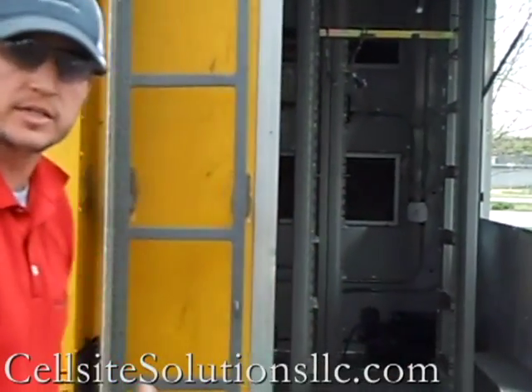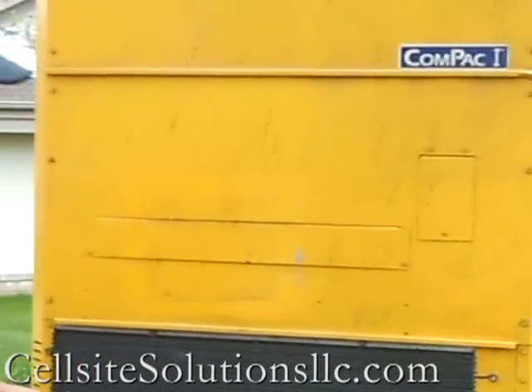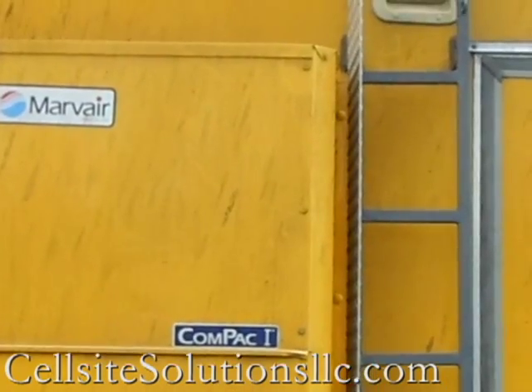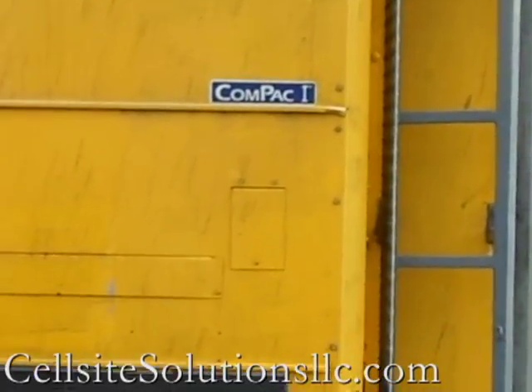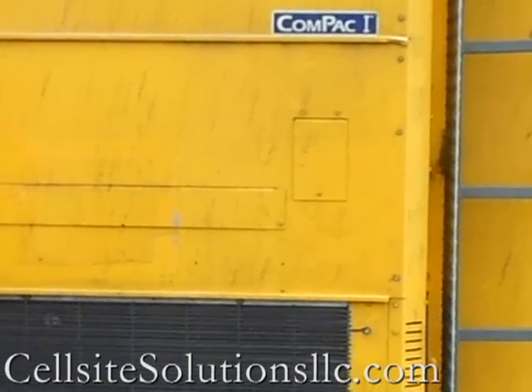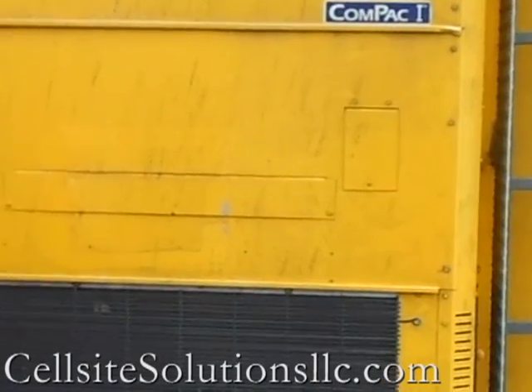There's an easy entry access door here in the back that gives you access to the inside. We've also got a second 3-ton Marvair air conditioning unit back here — these are AVP-36 air conditioning units. They're redundant, with a lead-line controller inside that will exercise and run both units if one should happen to fail.